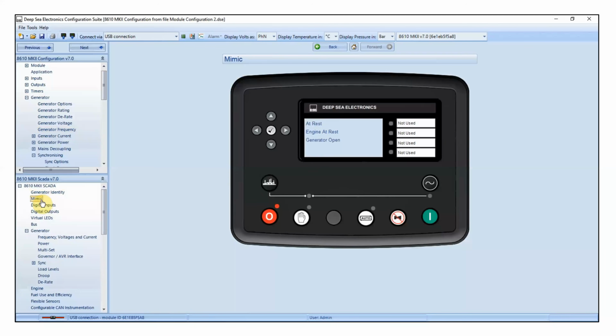I can already see there's another question coming, I'm guessing the customer is asking, in this setup procedure, is the DeepSea module wired to the generator's breaker? And yes, as part of this setup procedure, we are asking you to open and close the generator's breaker, because whilst this step is meant to be setting up the DeepSea module's control over the governor and AVR, we're not just testing the governor and AVR, we're testing other things. So us asking you to prove the DeepSea module can open and close the breaker is just another test. We'll carry on with the presentation now.